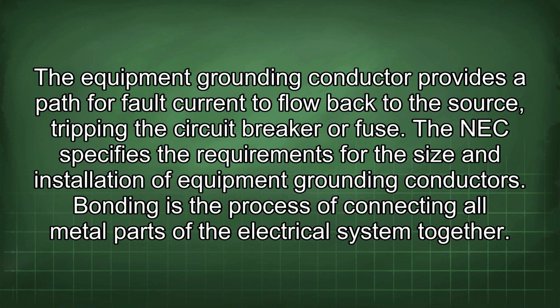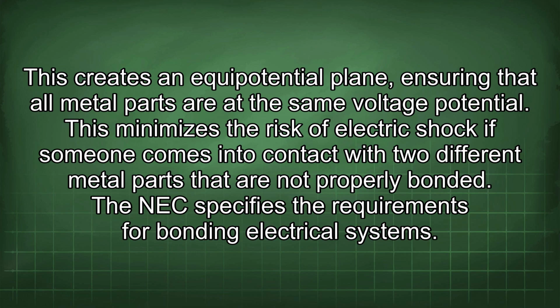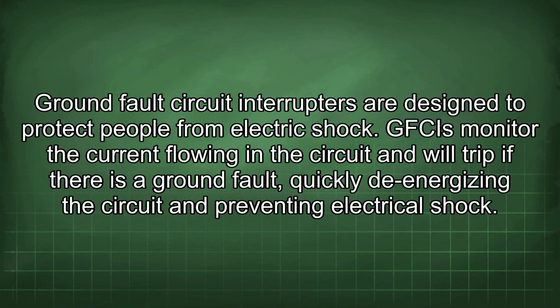Bonding is the process of connecting all metal parts of the electrical system together. This creates an equipotential plane, ensuring that all metal parts are at the same voltage potential. This minimizes the risk of electric shock if someone comes into contact with two different metal parts that are not properly bonded. The NEC specifies the requirements for bonding electrical systems. Ground fault circuit interrupters are designed to protect people from electric shock. GFCIs monitor the current flowing in the circuit and will trip if there is a ground fault, quickly de-energizing the circuit and preventing electrical shock.